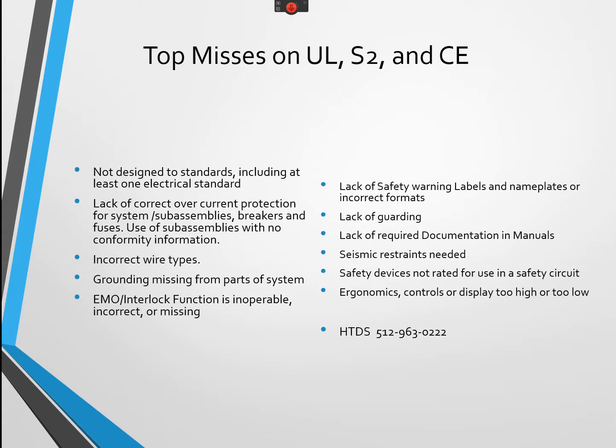Next one is grounding missing from parts of the system. Last year I went on a field evaluation for a piece of equipment, and they didn't have the secondary neutral of a transformer grounded to the equipment. That's required. If there is a ground lug coming off of a transformer or a compressor or anything else, ground needs to be landed to that and go to the ground bus. The old days of stacking 15 different ring terminals on a single vertical screw coming through the equipment doesn't work either. Also note that grounding to a stainless steel screw isn't going to get you where you need to be. Stainless steel has quite a bit of electrical resistance, so you're not going to be able to pass the grounding resistance testing if you have it built that way.